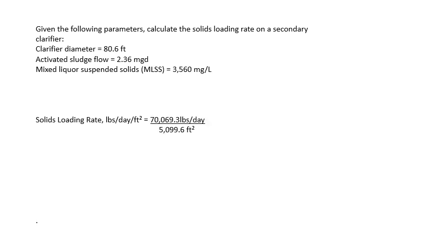So you end up with 70,069.3 pounds per day divided by 5,099.6 square feet. And your answer is 13.74 pounds per day per square foot.